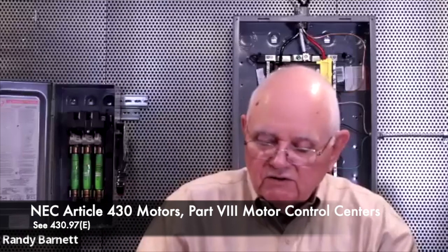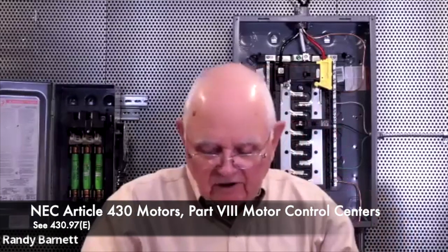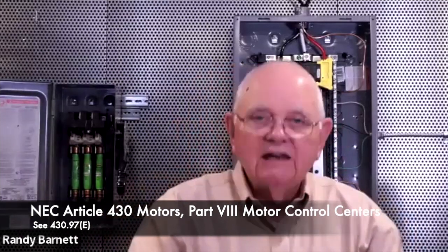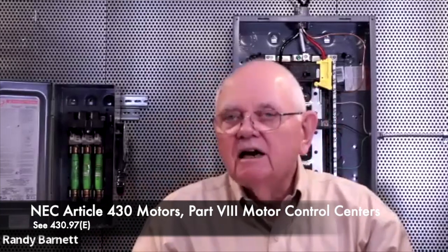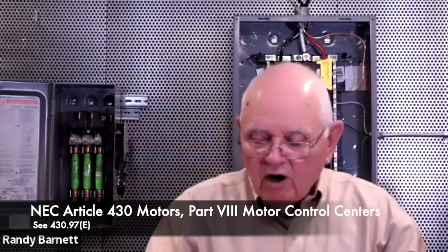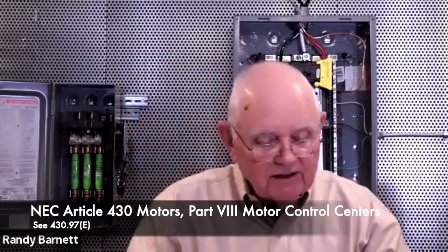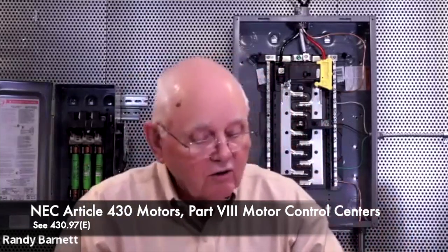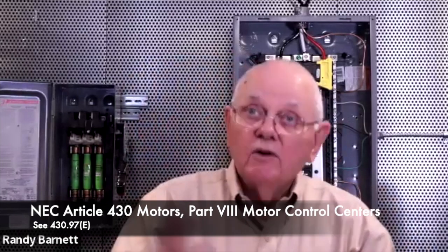230.62. Now, also sometimes we might use motor control centers for service equipment. So there's a requirement back in Article 430, Part 8 on motor control centers, and the requirement is found in 430.97. 430.97 is talking about bus bars and conductors in motor control centers. And once again, there's a requirement, 430.97(E) for barriers.